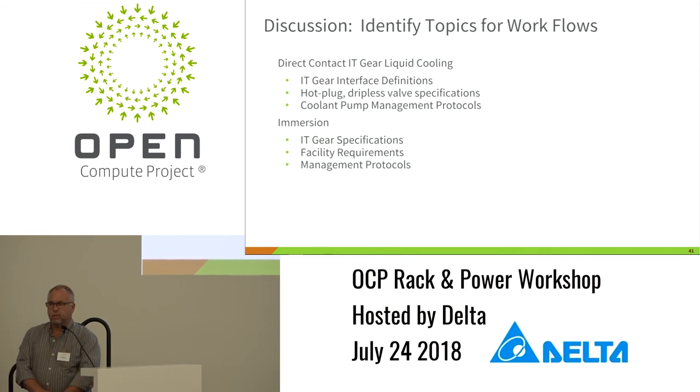And then again, on the facility side, the idea would be that regardless of the solution provider that's providing the emergent solution, we ought to have a common interface to the facilities and an expectation around that investment in the facility, because that investment is long-term, a 20-year life, right? So what type of water flows you need, do you need a chiller? Can you get away with a dry cooler? What kind of flow rates and delta T's and pressure deltas do you want to provide at the edge between the rack and the facility? So that would be another workflow.